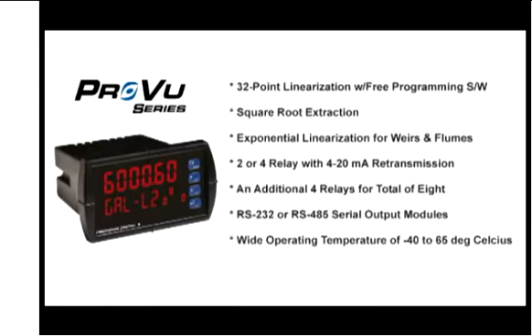The ProVu is available with either two or four relays and 4 to 20 milliamp output. We have external cards so you can add an additional four relays to the ProVu so you can control up to eight relays. There is also an RS-232 or RS-485 connection that can be used for serial communications. Finally, the ProVu will operate anywhere between minus 40 and 65 degrees centigrade.